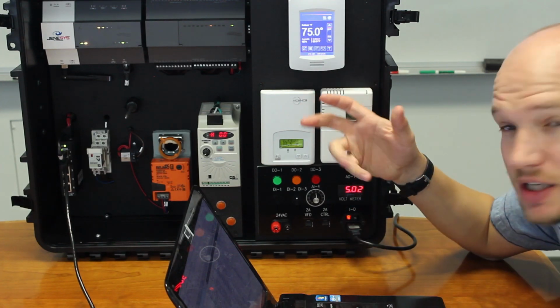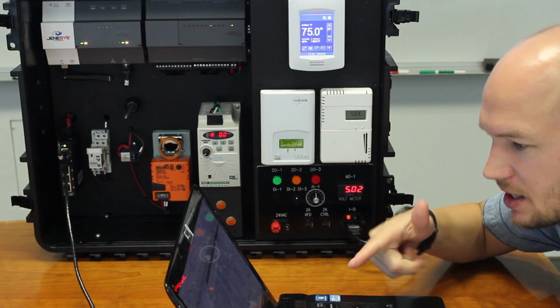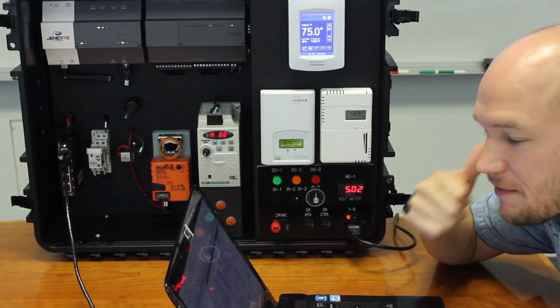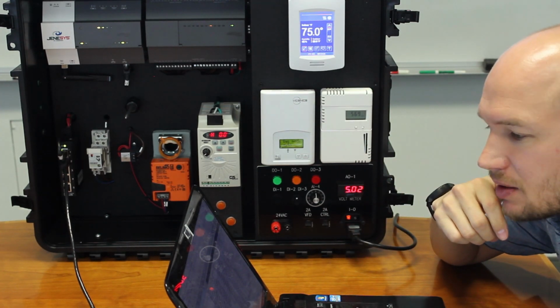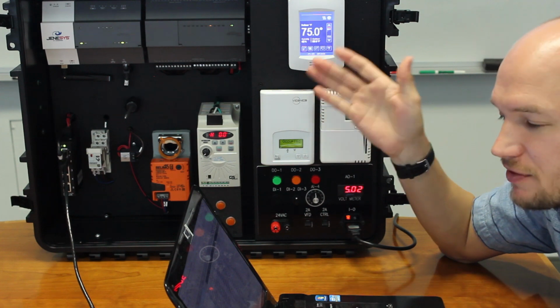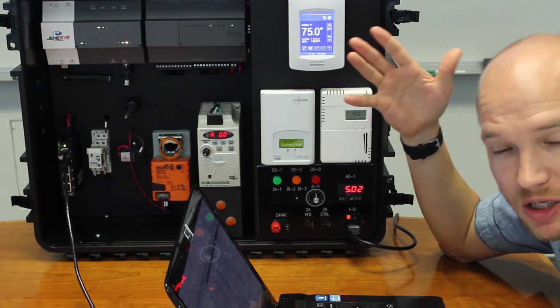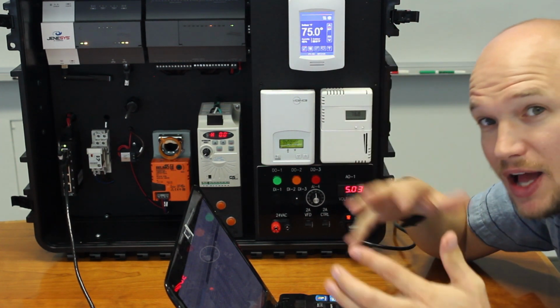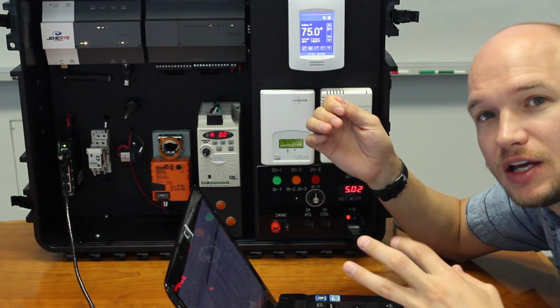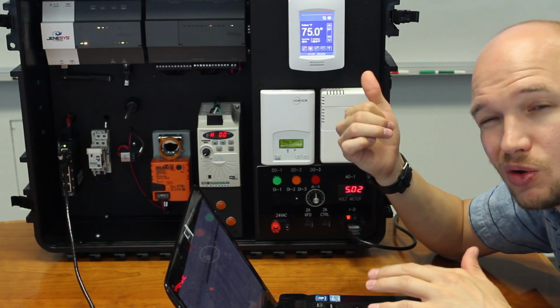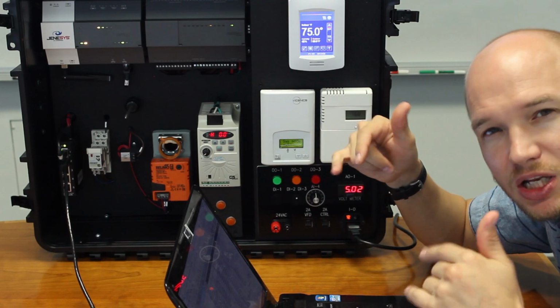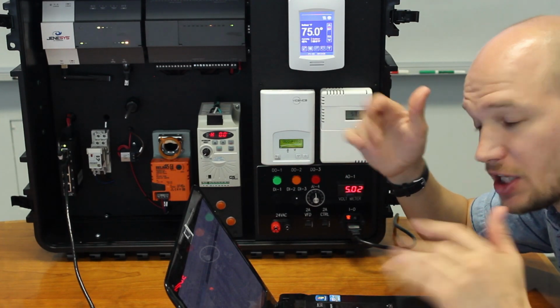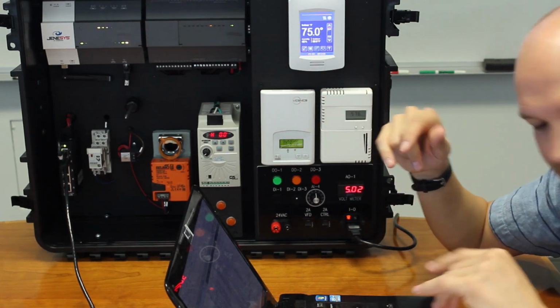So you can see I raised the temperature up on the thermostat. The heating demand went up to 73% on the computer. So again, if we lowered it down, the cooling demand would jump up as well. So that's all happening inside the JACE. The rooftop unit controller is a little bit slower. It took about a minute to reset, but eventually it does work and it shows up.